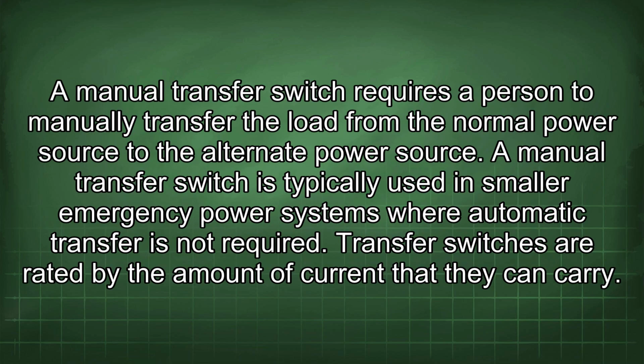A manual transfer switch requires a person to manually transfer the load from the normal power source to the alternate power source. A manual transfer switch is typically used in smaller emergency power systems where automatic transfer is not required. Transfer switches are rated by the amount of current that they can carry.